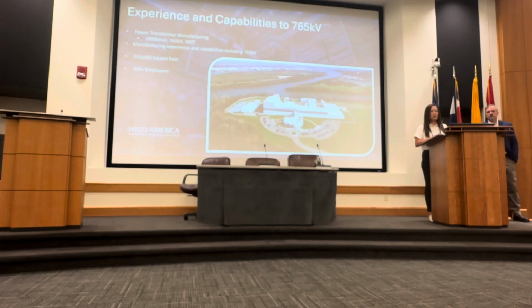How you lead your workers, how you manage your process, and the second thing is the testing. The testing capacity for 765 kV requires capacitors and generators ready for almost 1000 kV. We are one of the few facilities that can test up to 1100 kV in the USA. So you have the testing capability, you can manufacture this transformer, and verify any issues with the transformer right at this facility.